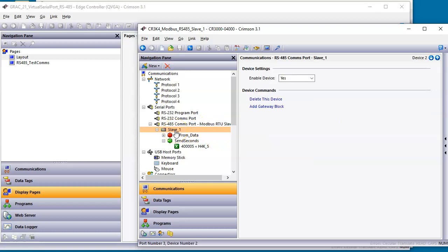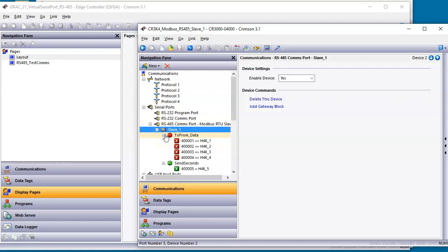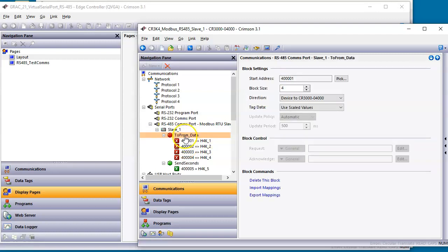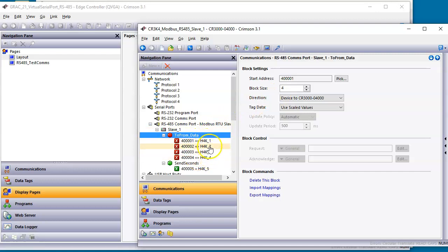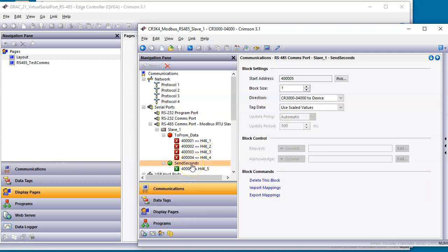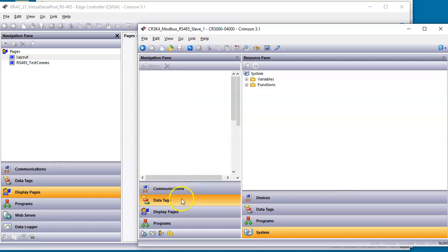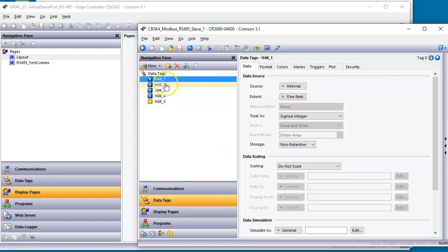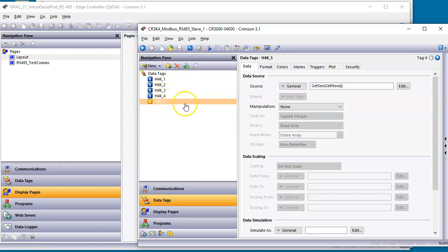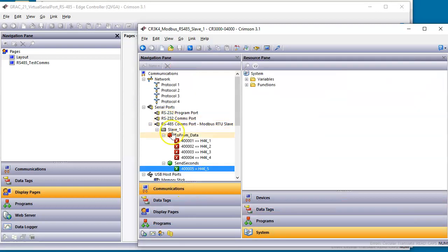I've got underneath here a couple blocks because I'm acting as a slave device or as a server. So I've got to configure my I/O. I've got one block that I call ToFromData and I start at 40,001. I'm doing four registers, 40,001 to 40,004. I've got some tags here called H4K underscore one to four. Notice the bi-directional here. Then I have another block here that's 40,005. This tag's a little different. I'm using get seconds parentheses get now. All that does is gets the real time clock, the seconds, and I'm using that to force across here at 40,005 the second counter.